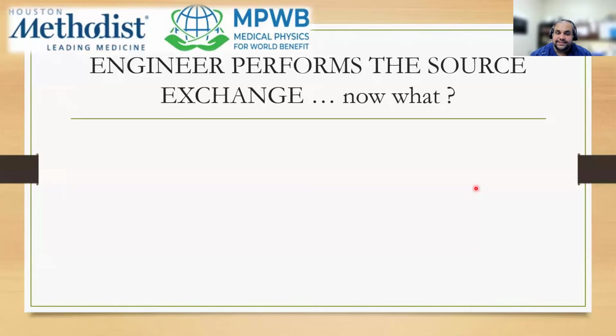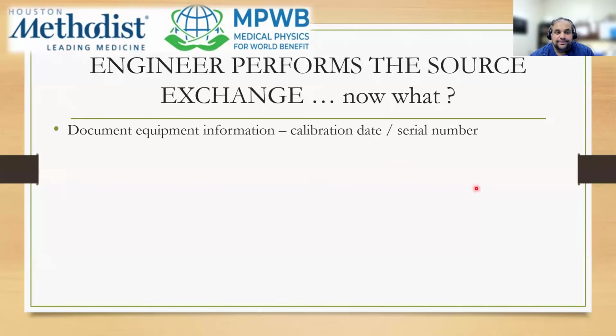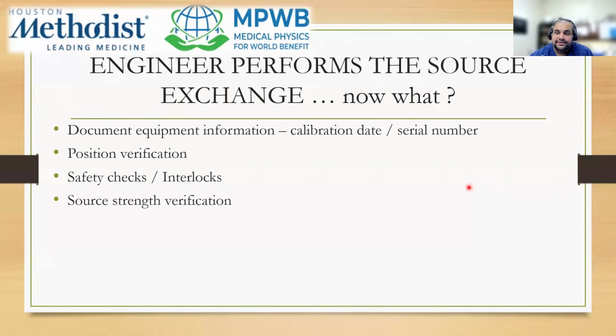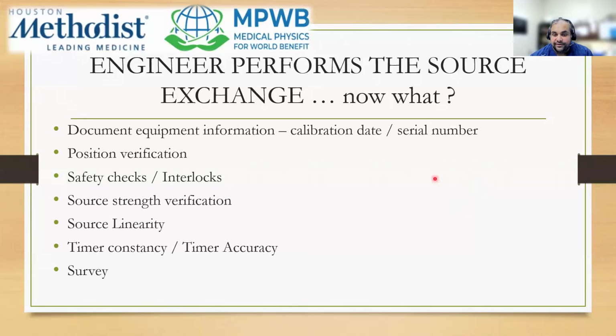So now the engineer performs the source exchange. Once they're done with their part, now what? There's documentation of equipment information. There's calibration date, serial number of the source. There's position verification that needs to be done. You have to test all your interlocks. There's source strength verification, source linearity, and of course your timer accuracy. And then survey around your vault and also around the afterloader. And then you create a decay table of your source.